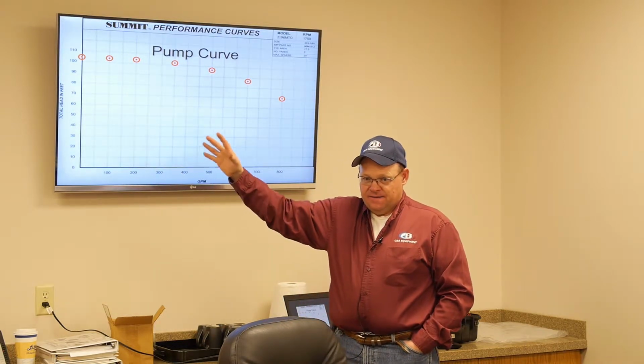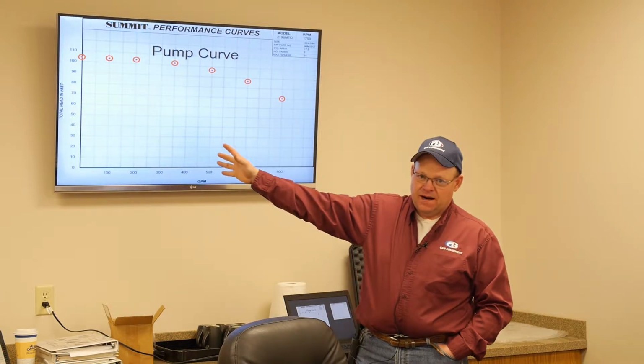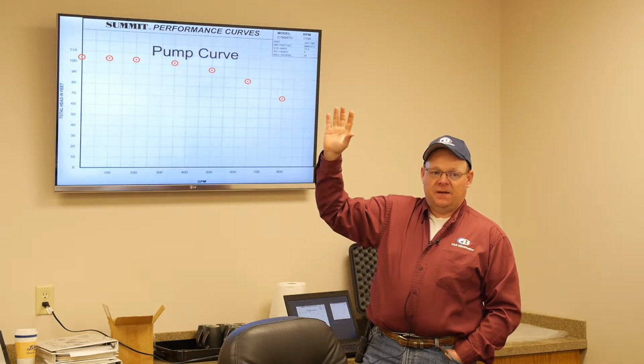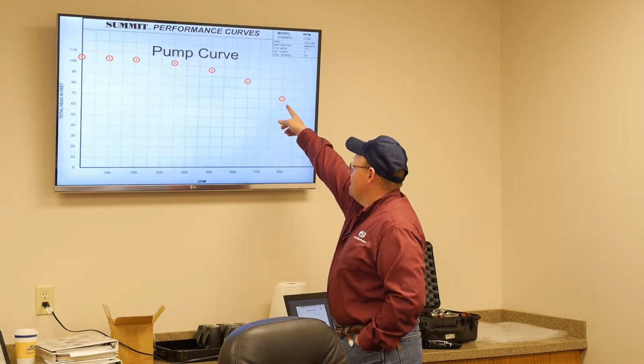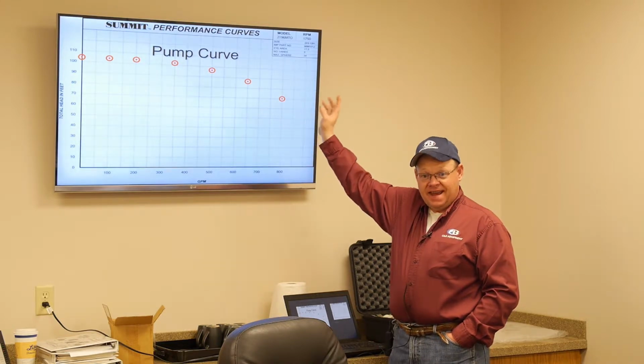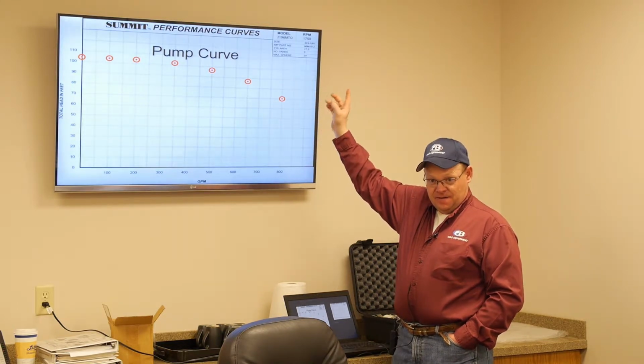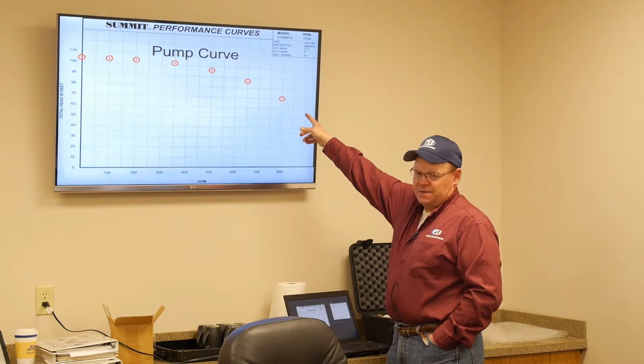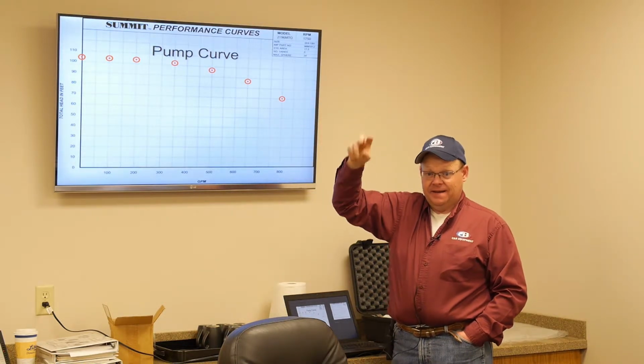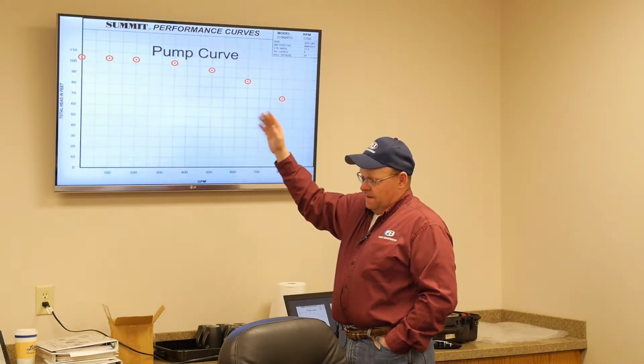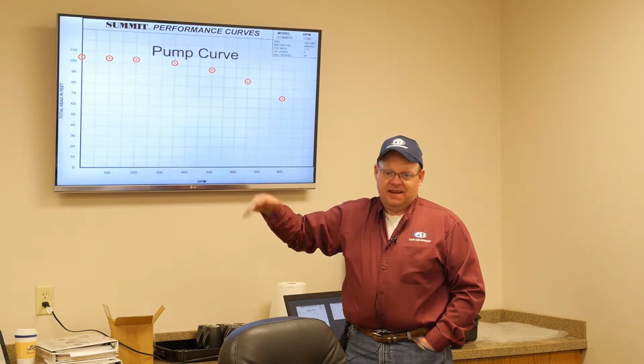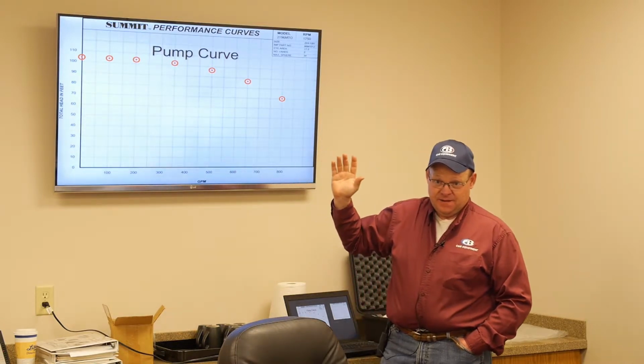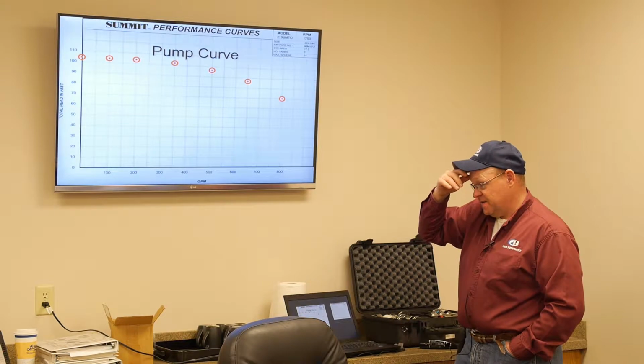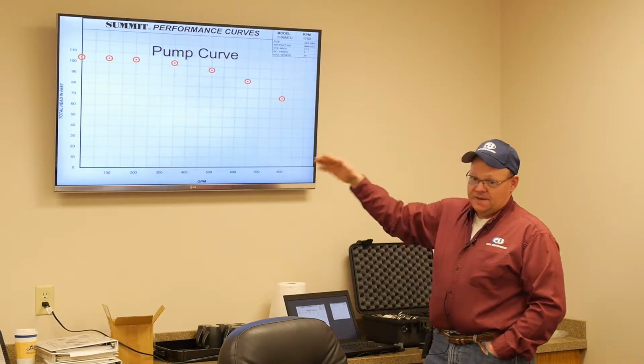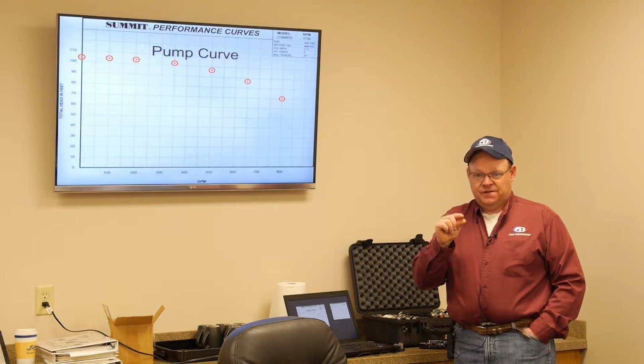The pump doesn't care. Let's back that up, because the pumps are not rated for that kind of burst pressure. Let's say we had 100 pounds of suction pressure, and out here we would have 130 pounds of gauge pressure. Does that make sense? Because we're producing 30 pounds of differential, or delta P, if you will. So from that standpoint, it doesn't care what its inlet is. It's only going to create this amount of pressure because it's a pressure creating device. But know and understand that that pump can move right to left on that curve very rapidly with minute pressure changes.